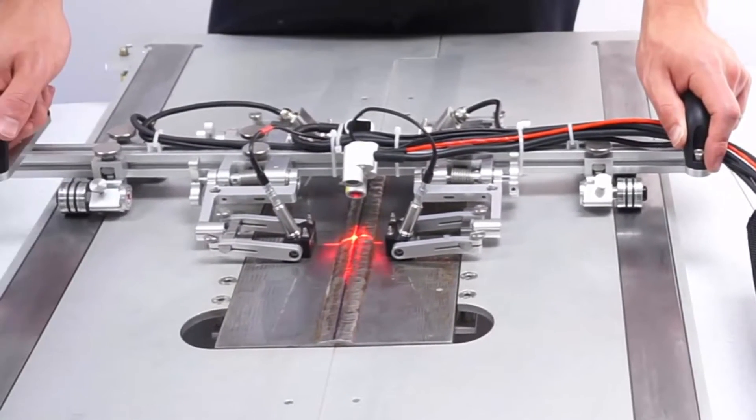The solution is based on the Topaz 16 phased array system and weld crawler. It combines the use of pulse echo phased array and time of flight diffraction techniques, commonly known as TOFD, all in a single inspection sequence.